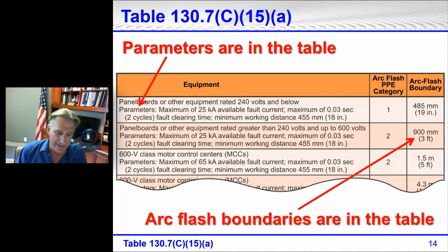All right, Table 130.7(C)(15)(A). This table gives us the information, like the top one here, panelboards or other equipment rated 240 volts and below. The next line is greater than 240 up to 600 volts. This is the table that has the parameters in it. It has the maximum available fault current, and for the top two that is 25,000 amps, 25 kA. It has a maximum clearing time of 0.03 second, or 2 cycles. And this also shows the working distance of 18 inches. So if your parameters are not within those limits, using these tables is not permitted.